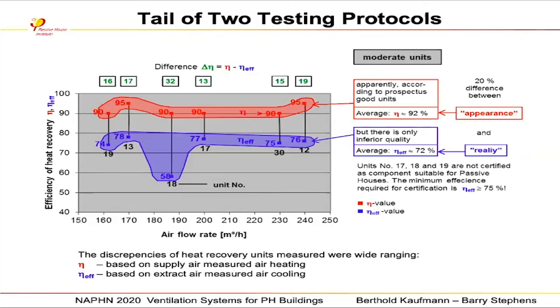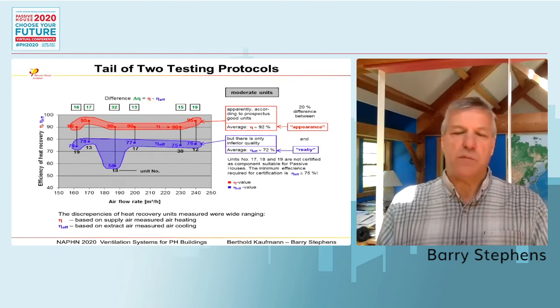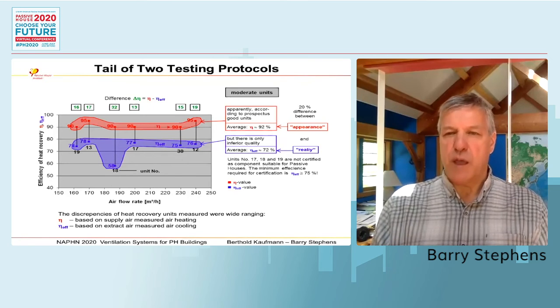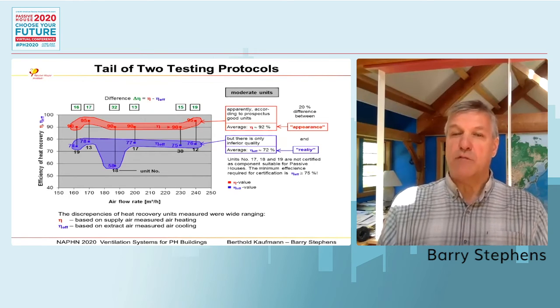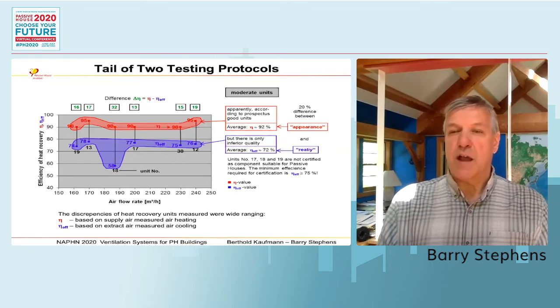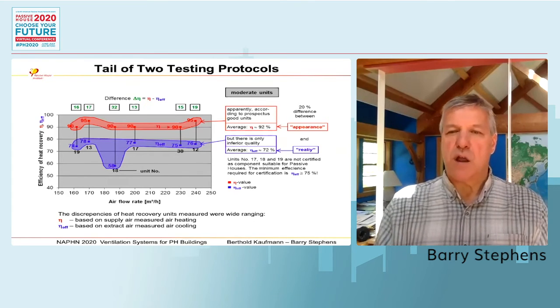Those 2 standards are completely different. One of the big takeaways with this slide: these are 6 units that were measured to those 2 standards. What you see across the top in those small boxes is the percentage difference between Passive House, the blue lower numbers, and HVI, the larger red upper numbers. You can see the differences are 16%, 17%, 32%, 13%, 15%, 19%. One of the challenges is you can't take a standard correction and just say, okay, I'm going to take my HVI number and just change it by 12% and go with that. You have to test, because these units behave differently, and it's really critical. That's a big takeaway, and we're working to get Passive House tested numbers certified here in North America. We're working with labs, and HVI's lab in Canada can now test residential units to Passive House, and we're working with the AHRI labs to do the same.